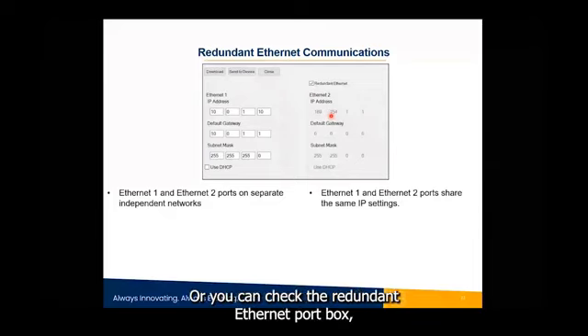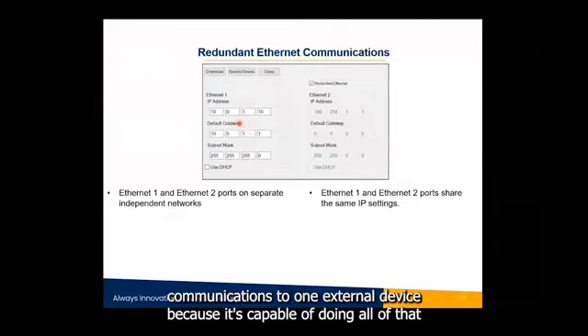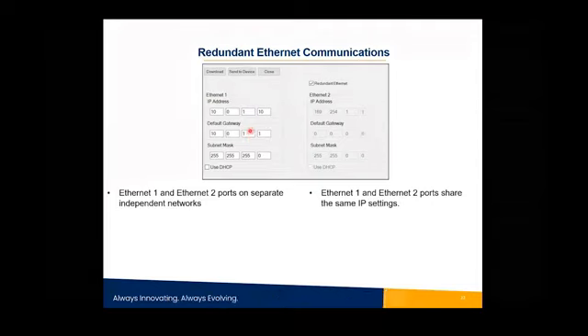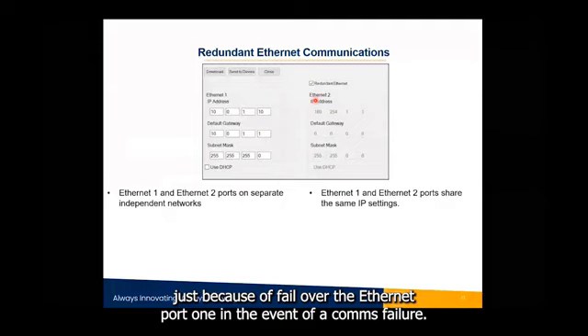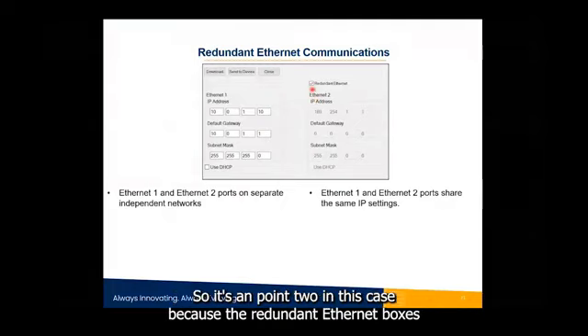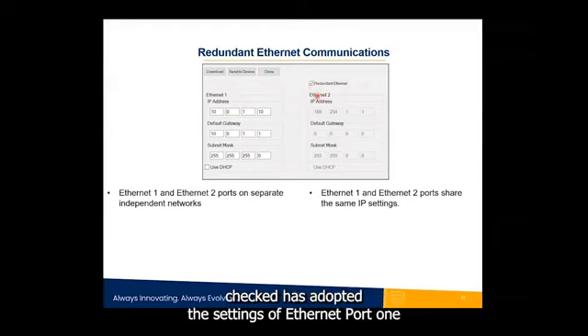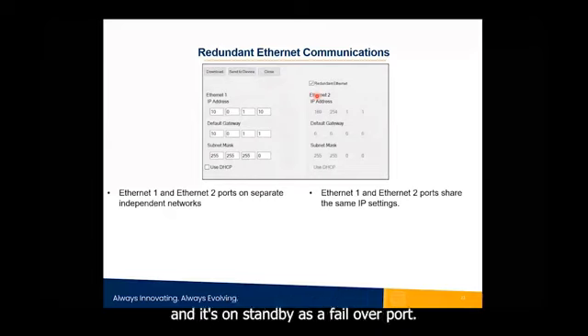Or you can check the redundant Ethernet port box and use Ethernet port 1 for everything, including load sharing and Modbus communications to an external device, because it's capable of doing all of that. In that case, Ethernet port 2 just becomes a failover to Ethernet port 1 in the event of a comms failure. So Ethernet port 2 in this case, because the redundant Ethernet box is checked, has adopted the settings of Ethernet port 1, and it's on standby as a failover port.